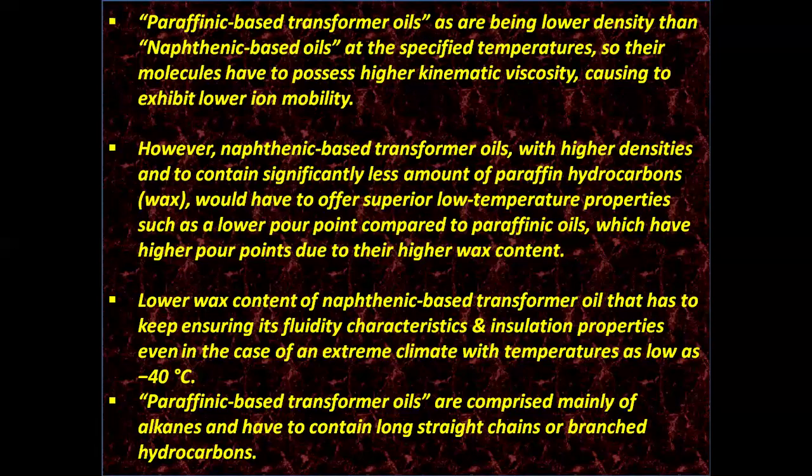The lower wax content of naphthenic based transformer oil ensures its fluidity, characteristics, and insulation properties, even in extreme climates with temperatures as low as minus 40 degrees centigrade.